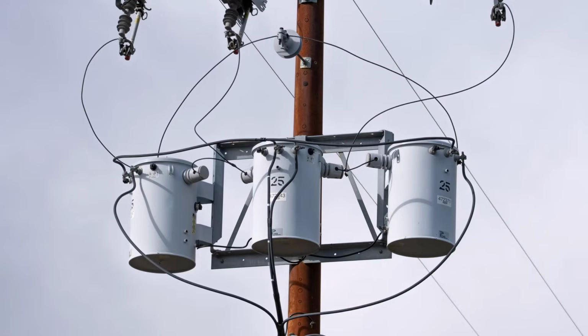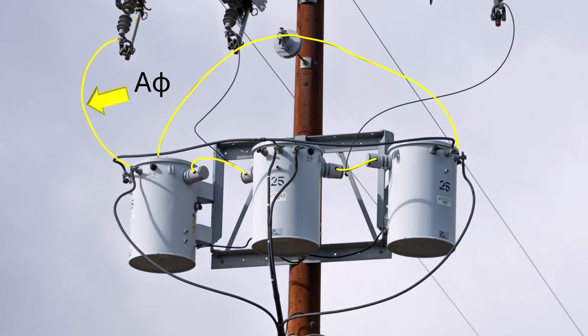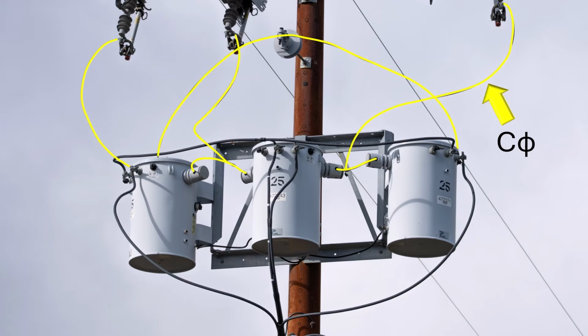You can see the primary delta connection in this image. The 2 transformers on the left are connected with a short jumper wire. The 2 transformers on the right are connected with another short jumper wire. The 2 outer transformers are connected with a long jumper wire. This long jumper wire is connected to the A phase primary conductor with a lead wire. The connection is hidden behind the tank in the image. The short jumper wire on the left is connected to the B phase primary conductor. And finally, the jumper on the right is connected to the C phase conductor.